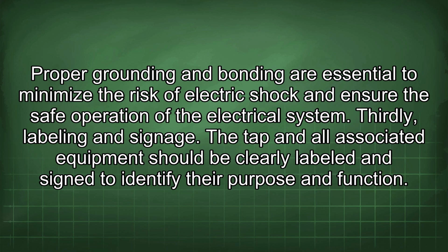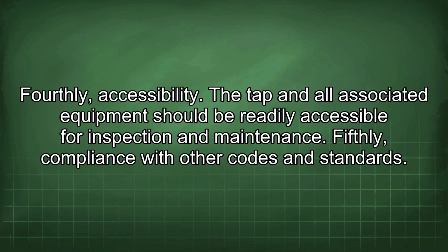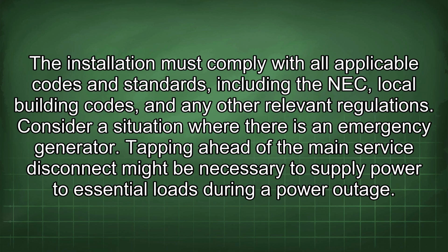Thirdly, labeling and signage. The tap and all associated equipment should be clearly labeled and signed to identify their purpose and function. Fourthly, accessibility. The tap and all associated equipment should be readily accessible for inspection and maintenance. Fifthly, compliance with other codes and standards. The installation must comply with all applicable codes and standards, including the NEC, local building codes, and any other relevant regulations. Consider a situation where there is an emergency generator.